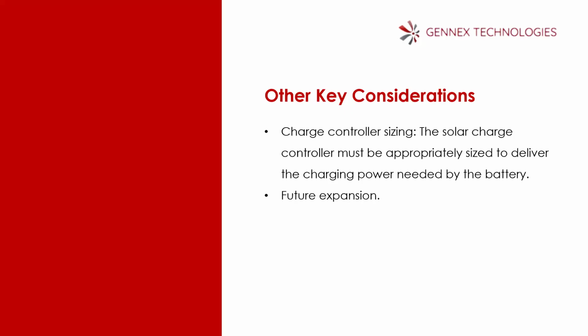So consider future expansion. Don't just limit the capacity of the charge controller to just one battery. Your client may want to increase the batteries to 4 at the end of the day. For instance, if you're operating with a 10 kilowatt hour battery and your client goes to 4 units of that, don't limit your charger to just one. Look for a charger that has capacity to handle 2 or 3. Even if it cannot handle everything successfully and you need additional capacity later, don't just limit it at the first stage.